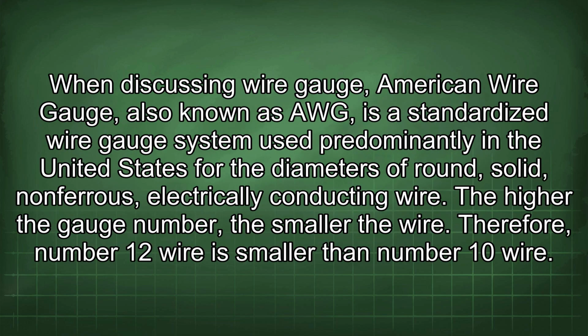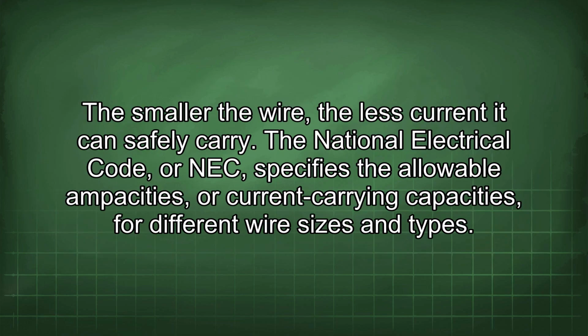When discussing wire gauge, American wire gauge, also known as AWG, is a standardized wire gauge system used predominantly in the United States for the diameters of round, solid, non-ferrous, electrically conducting wire. The higher the gauge number, the smaller the wire. Therefore, number 12 wire is smaller than number 10 wire. The smaller the wire, the less current it can safely carry.